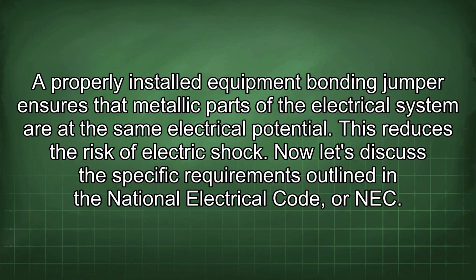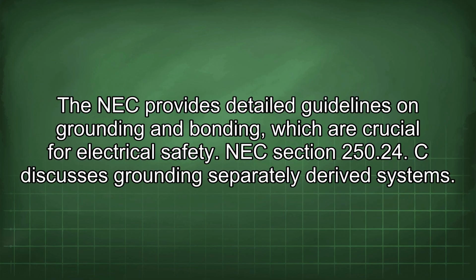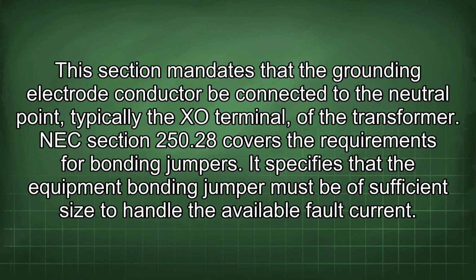Now let's discuss the specific requirements outlined in the National Electrical Code, or NEC. The NEC provides detailed guidelines on grounding and bonding, which are crucial for electrical safety. NEC Section 250.24(C) discusses grounding separately derived systems. This section mandates that the grounding electrode conductor be connected to the neutral point, typically the XO terminal, of the transformer. NEC Section 250.28 covers the requirements for bonding jumpers. It specifies that the equipment bonding jumper must be of sufficient size to handle the available fault current.